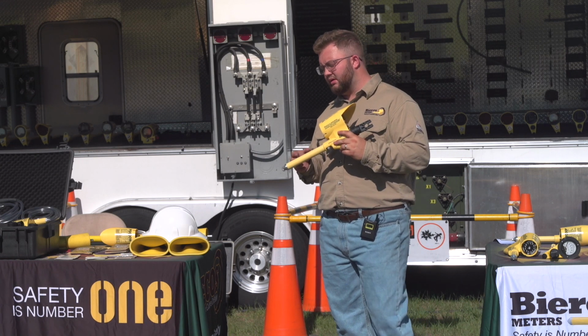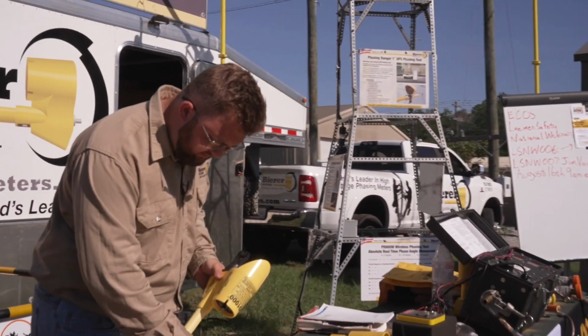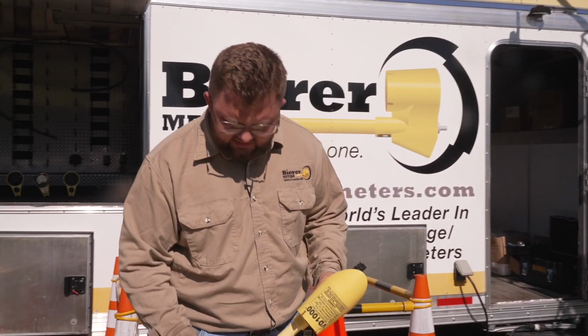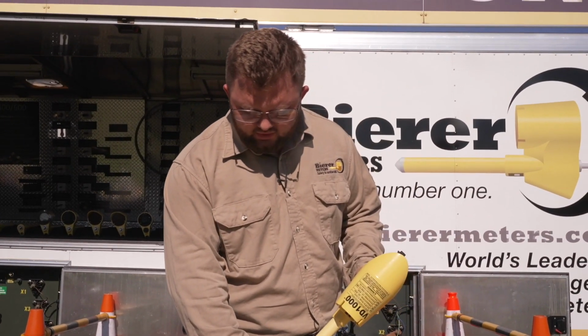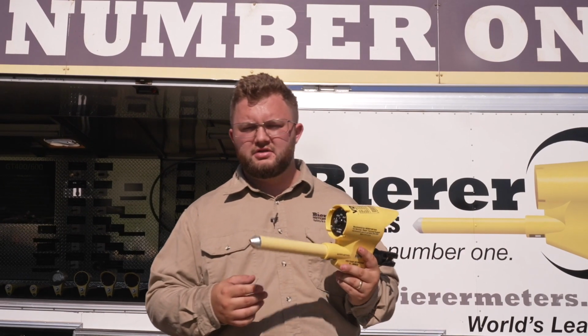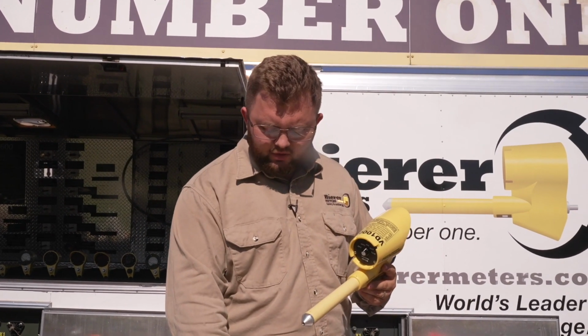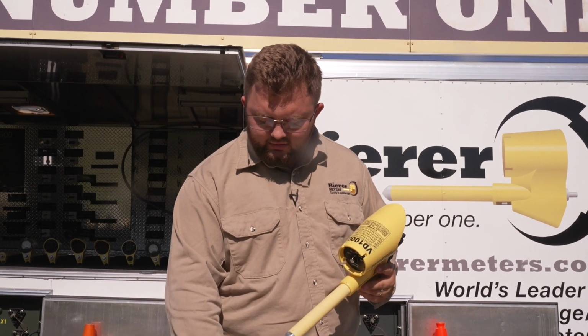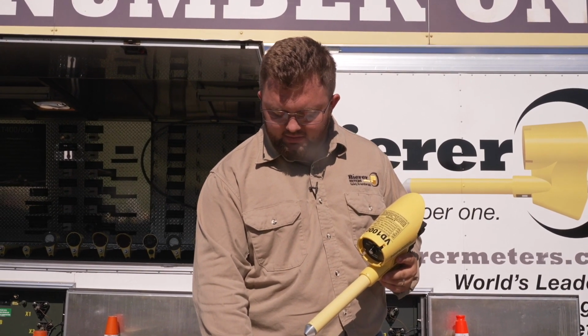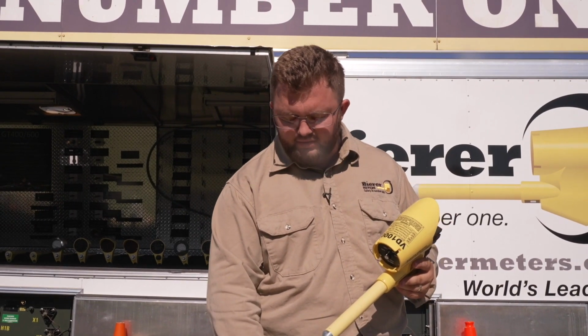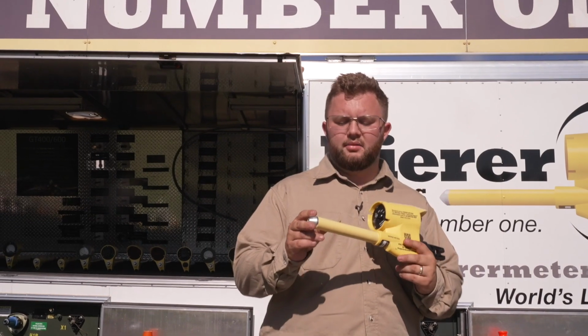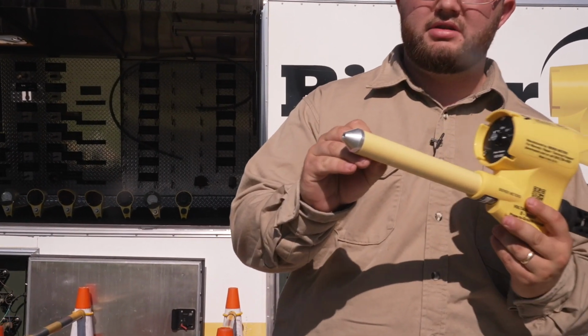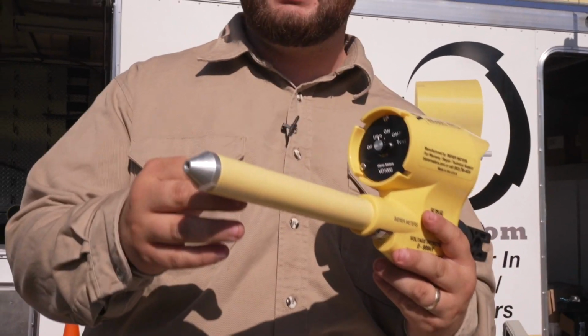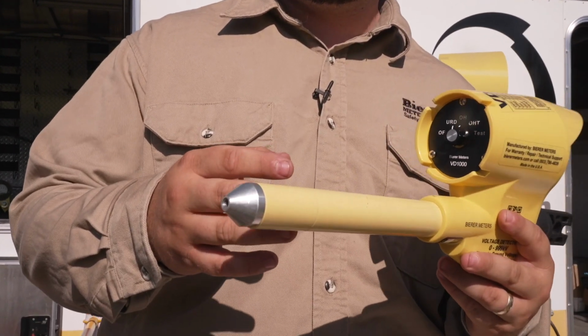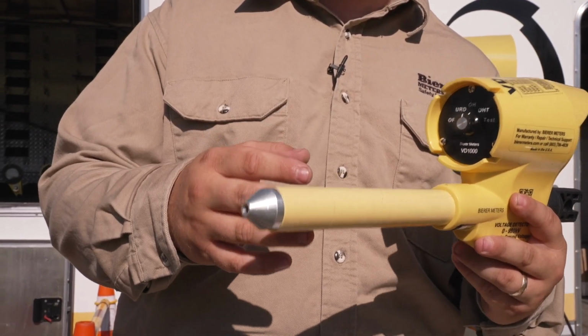Also we'll go into our line limiting mark. So ASTM F1796, if you go down to 3.1-9, there's a line limiting mark. It's a recommendation by ASTM for voltage detector manufacturers to put a line limiting mark on the device in a distinctive location to indicate to the user a physical limit to where the detector may be inserted between live components or touch them. So that's going to be here below the line limiting mark. We put it down about 2.5 inches from the end of the probe tip. That's a recommendation of where you're not going to want to pass with a potential or a potential ground.